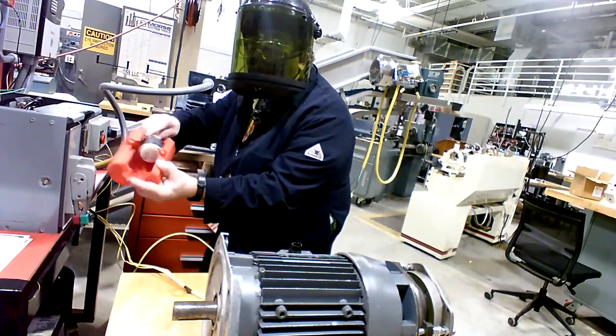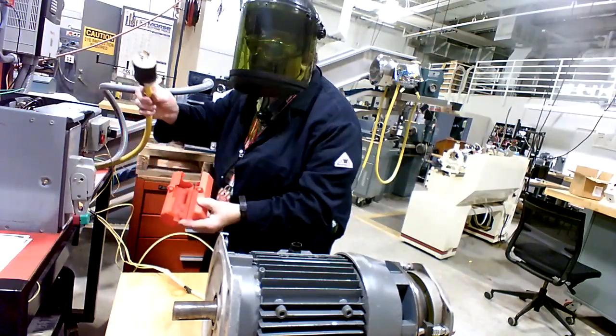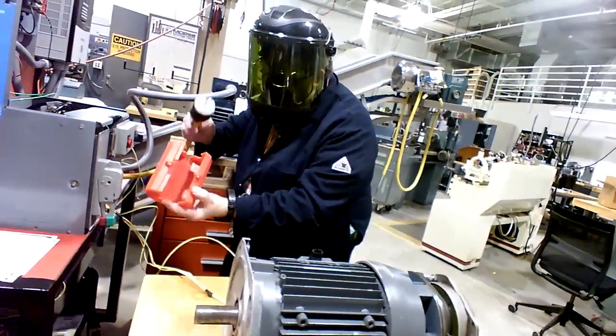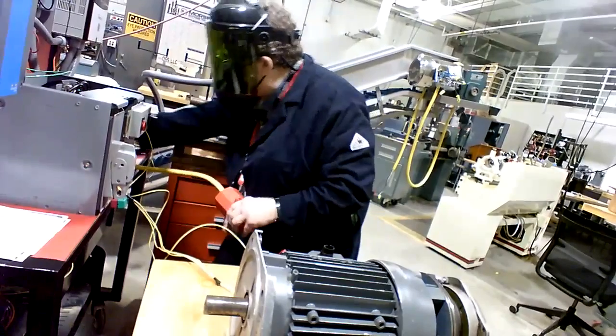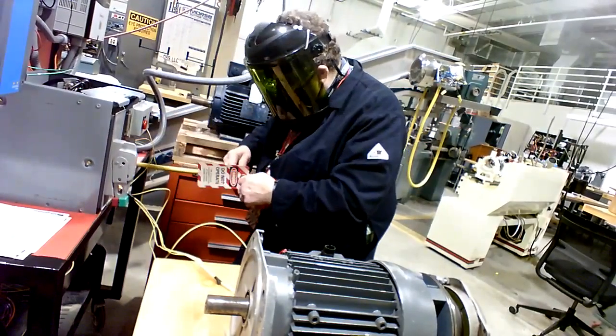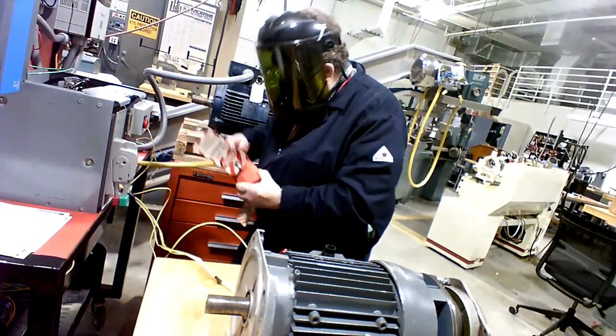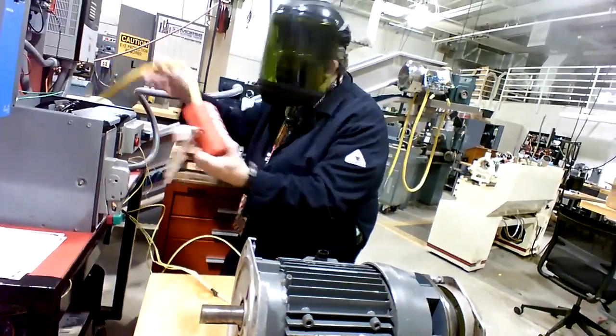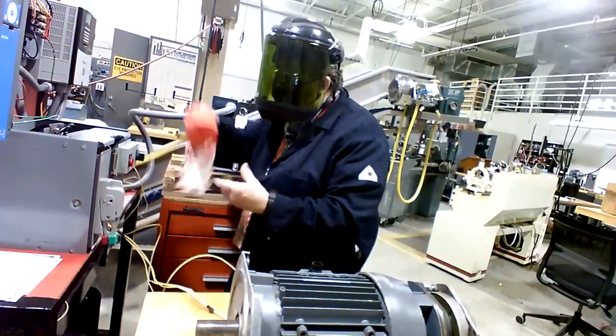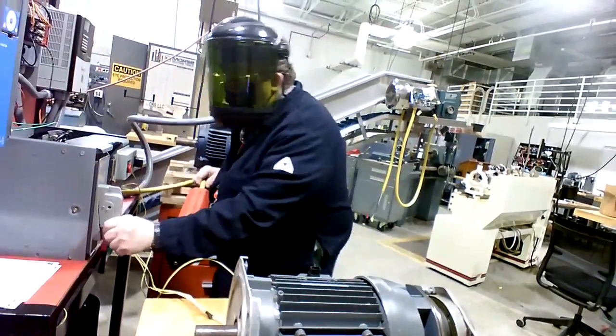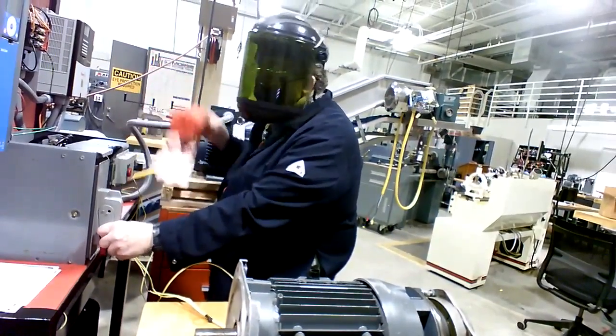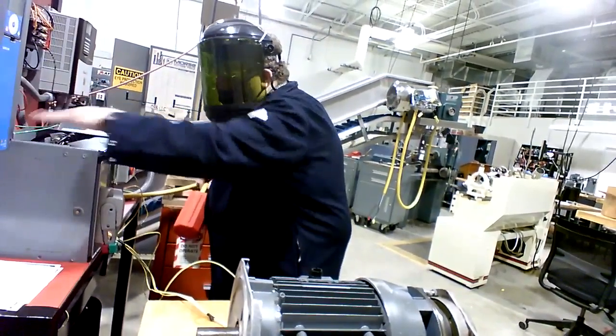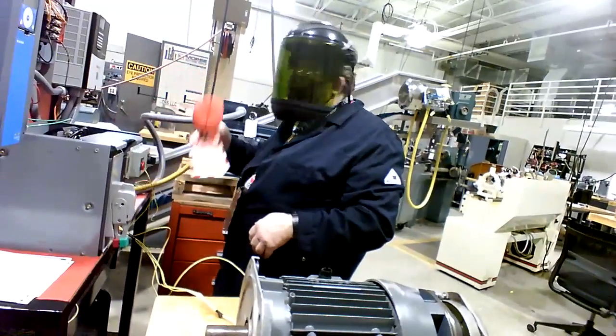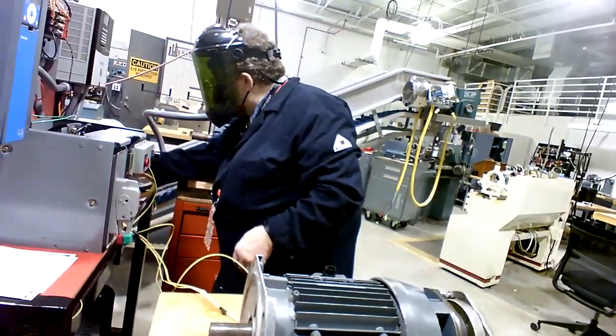We're putting a lockout device on here. They've got lockout devices for most anything. That's a big old 480-volt three-phase plug. We've got a can for that. And so we're locking out the pigtail for the plug instead of locking out the handle. If we lock this out, there's still a risk of somebody plugging that in, that's big and hot going in. So the safest thing is really to get the pigtail locked out.